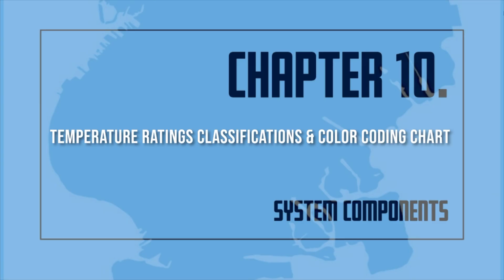black. For a maximum ceiling temperature of 475 degrees Fahrenheit, with a temperature rating of 500 to 575 degrees Fahrenheit, and a temperature classification of ultra high, with a frame color code of orange, the glass bulb color would also be black. For a maximum ceiling temperature of 625 degrees Fahrenheit, with a temperature rating of 650 degrees Fahrenheit, and a temperature classification also of ultra high, with a frame color code of orange, the glass bulb color would also be black. See page 28 in the New York Fire Department transcript for a printable chart.